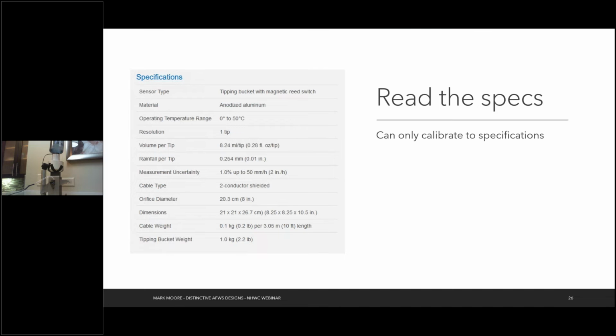So one thing to be aware of for calibrations, and if you've seen any trainings that I've done, you've heard me say this a lot: read the specs. Anytime you're calibrating, and it doesn't matter if it's a tipping bucket, a pressure transducer, a bubbler, a radar, a soil moisture sensor, your accuracy has to be based off of the specifications of the sensor. We can't say that this tipping bucket has to be accurate to within 0.5% if the specs only say it's accurate to within 3%. We have to match our expectations to what the specifications of the sensor are.